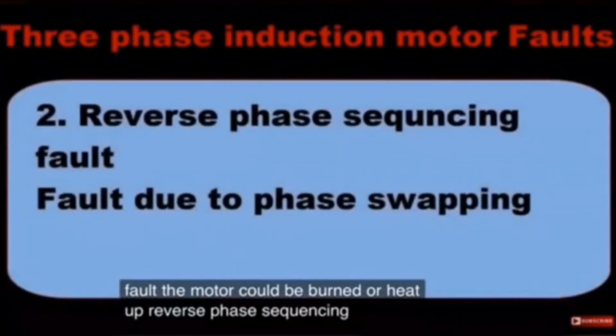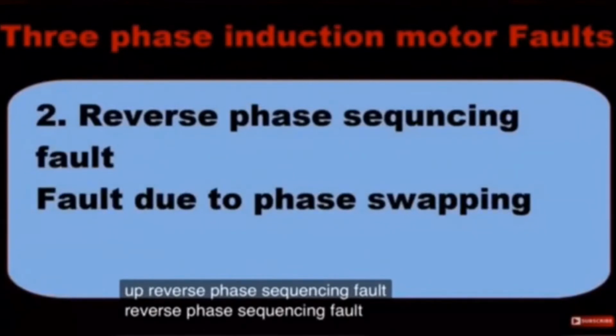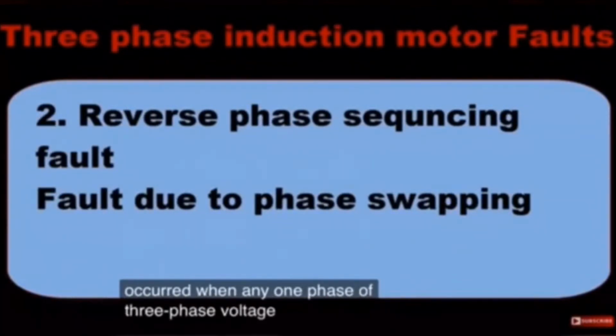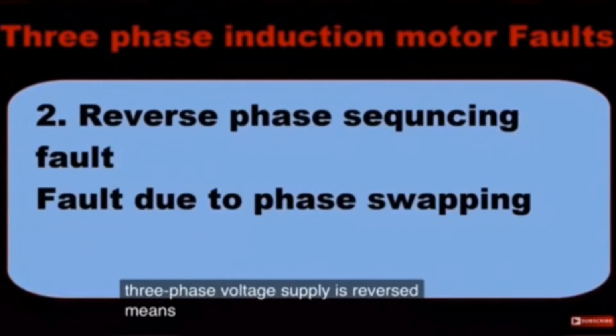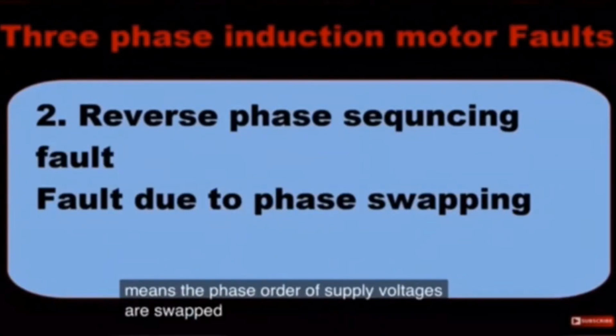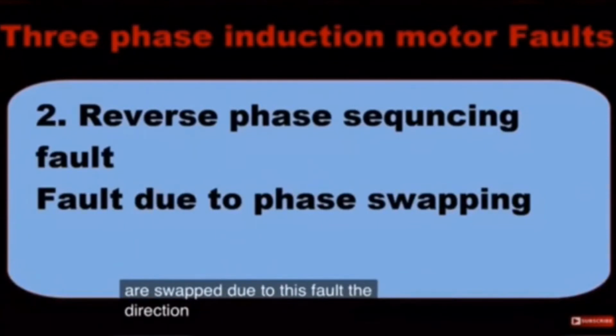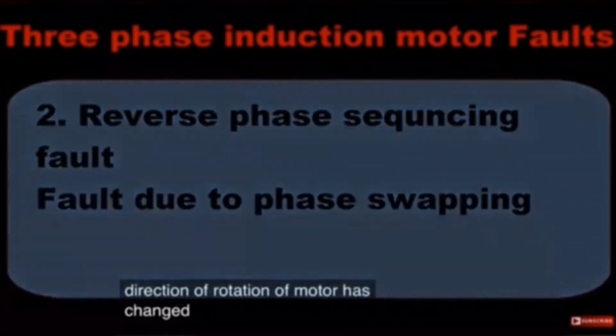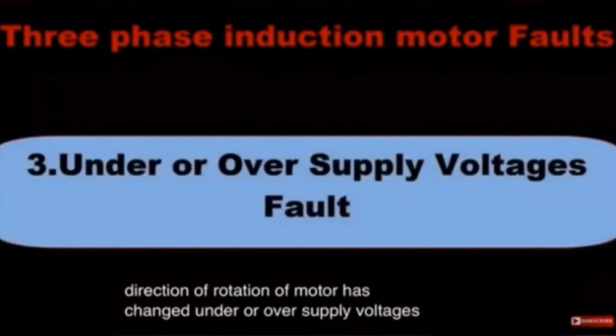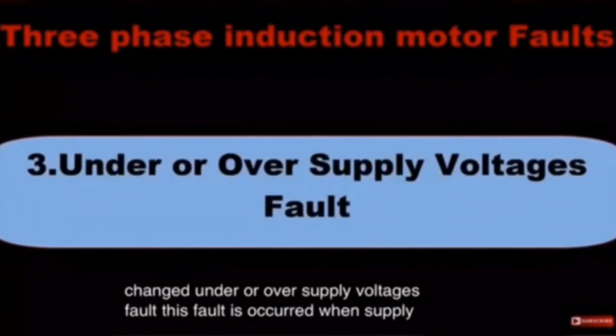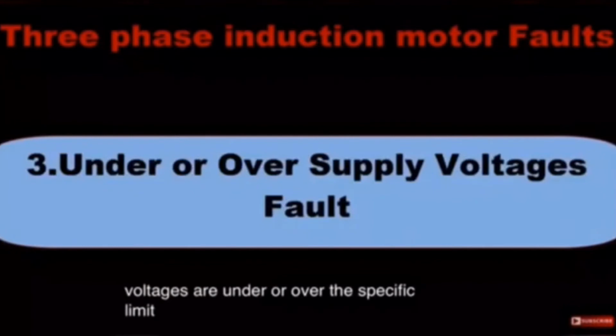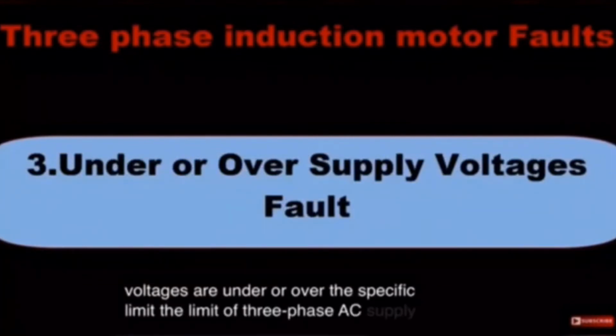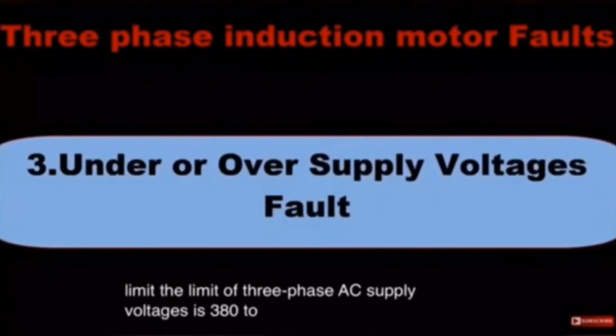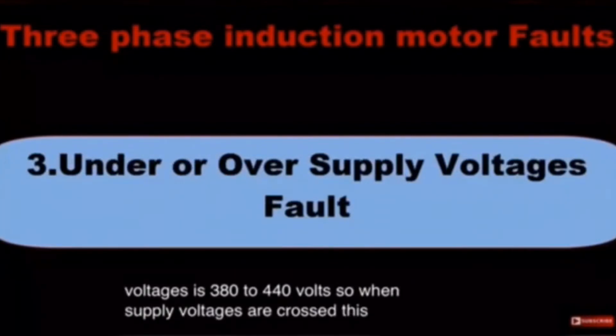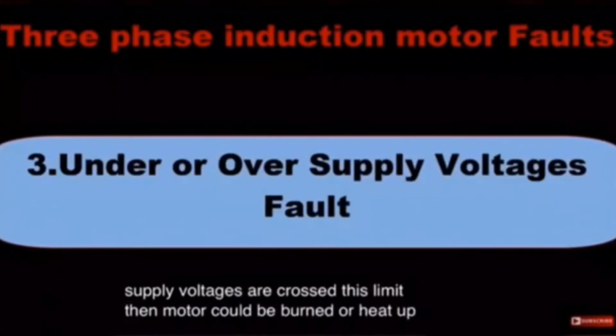Reverse phase sequencing fault. Reverse phase sequencing fault occurs when any one phase of 3-phase voltage supply is reversed, meaning the phase order of supply voltages are swapped. Due to this fault the direction of rotation of motor has changed. Under or over supply voltages fault. This fault occurs when supply voltages are under or over the specific limit. The limit of 3-phase AC supply voltages is 380 to 440 volts. So when supply voltages cross this limit, then motor could be burned or heat up.